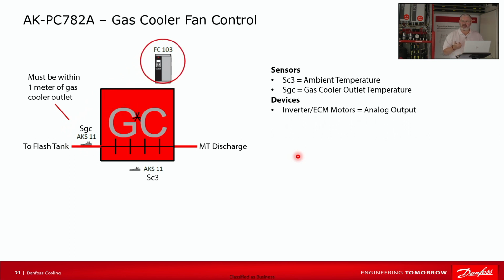And then devices, we simply have either an inverter or a 0 to 10 volt signal going to ECM fan motors. Something to note on that signal, typically for transcritical systems, people invert that and they actually control from 10 to 0, where 10 means fans off, 0 means full 100% capacity, so that if you were to lose that connection for any reason or upon controller failure, your gas cooler fans will ramp to wide open. So those are our sensors and our device.